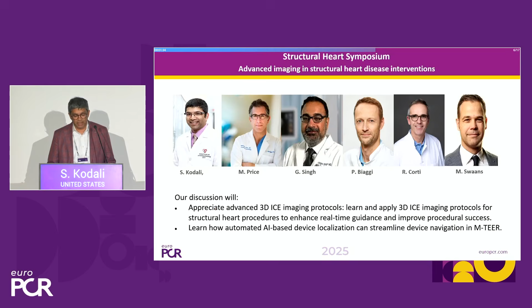We already talked about the panel, but just in a few minutes, I want to talk about the ICE system. This is the VeriSight 3D ICE catheter. It's a 9 French device. There are 2 steering wheels and a clutch knob which holds the curves. This is a single-use disposable unit. It connects to the Philips machine with a reusable cable. There's no bag you need to put on it because this part just comes off the field, so there are no issues with sterility.